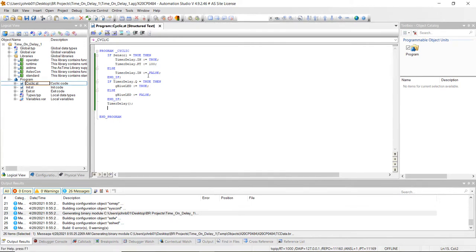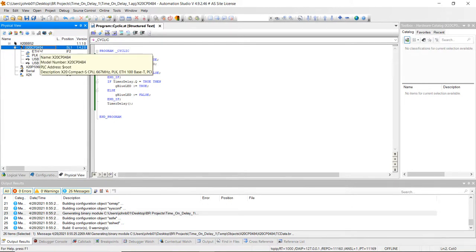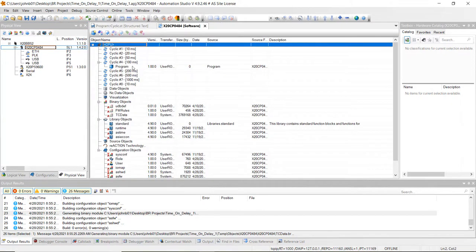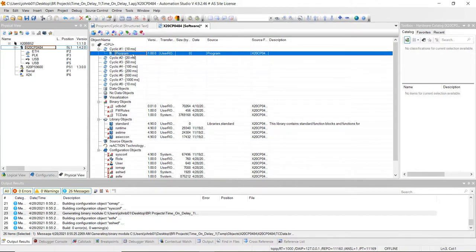One other crucial step is setting the cyclic. Right now the cyclic could be running at a different rate. Go over and right click on the controller in physical view and click on software. You'll notice that the program we created is in cyclic number four, which means it's going to scan every 100 milliseconds. If we want it in cyclic number one, where it's scanning every 10 milliseconds, that's a way better deal. Just left click on it and drag it up under cyclic number one — now this program will be scanned every 10 milliseconds.